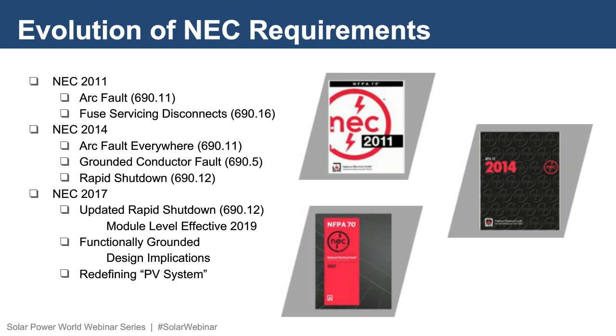In the 2014 code cycle, the arc fault requirement was revised to be included on all PV systems regardless of their location. Ground fault protection was revised to have a more thorough requirement of detecting ground faults in the grounded conductor. And as all of us know, the requirement for rapid shutdown was first introduced.